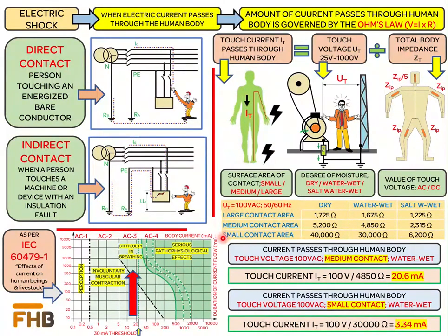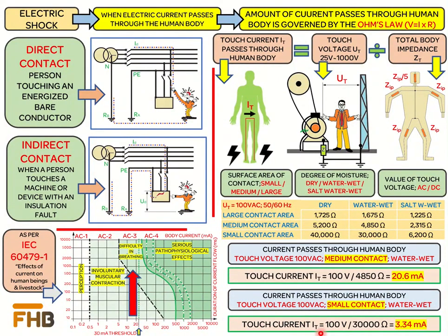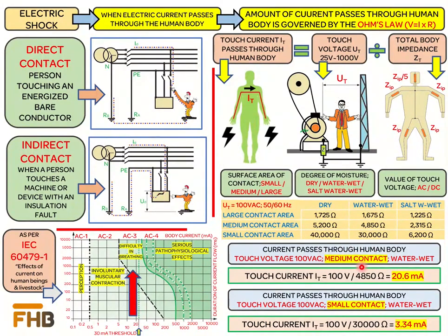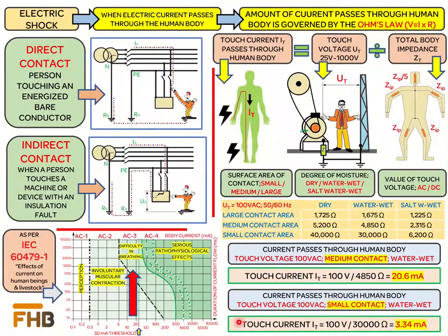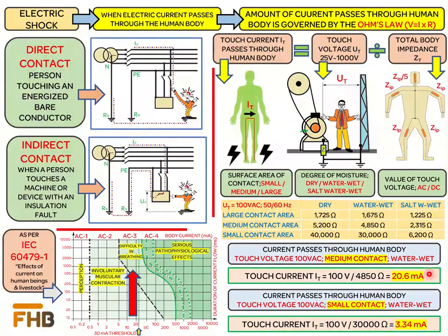Since the main aim of our discussion is to find the danger that electric current can cause to a human body, we will now calculate the value of electric current passing through a human body under different conditions. For this comparison, the surface area is variable while the touch voltage is constant at 100 V AC and degree of moisture is constant at wet condition. From the calculation, for a medium surface area the touch current is found to be 20.6 milliamperes, and for a small surface area it is 3.34 milliamperes. This shows that a medium contact with a live surface results in more current flowing through the body compared to a small surface area contact.